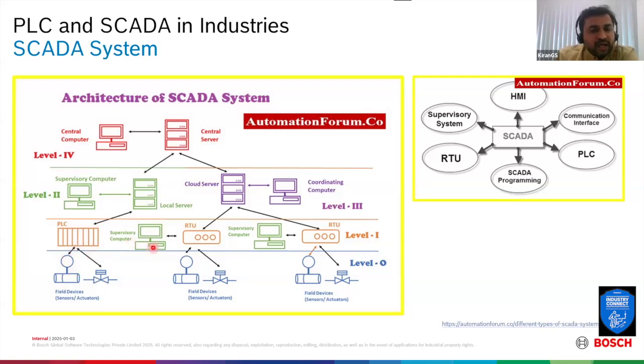Similarly, we can have other systems, simply a remote terminal unit, which need not have a powerful PLC. So the field level devices can be termed as level 1. Then comes a newer way of introducing this to a next higher level, what we call a supervisory computer. From a level 3 angle, you will have a supervisory computer or a cloud server — all these end up in level 3. Finally, level 4 will have a central server and all.